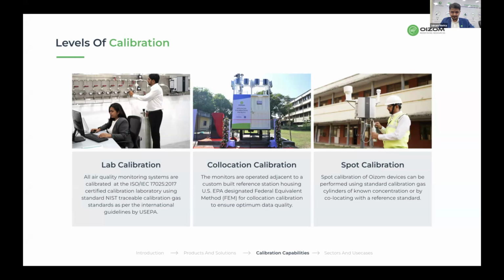into the systems. In case the customer needs to do periodic calibration, our systems, whenever there are seasonal changes, have an automated AI-based compensation correction algorithms applied for over-the-air calibration. The only requirement that we have for that is the systems have to be online. So in case you are pitching to a customer, please ensure that even if they do not want the systems connected to the internet, it is not a problem. However, maybe once a quarter or once in 6 months, we should try to get the systems online so that we can do over the air calibration.